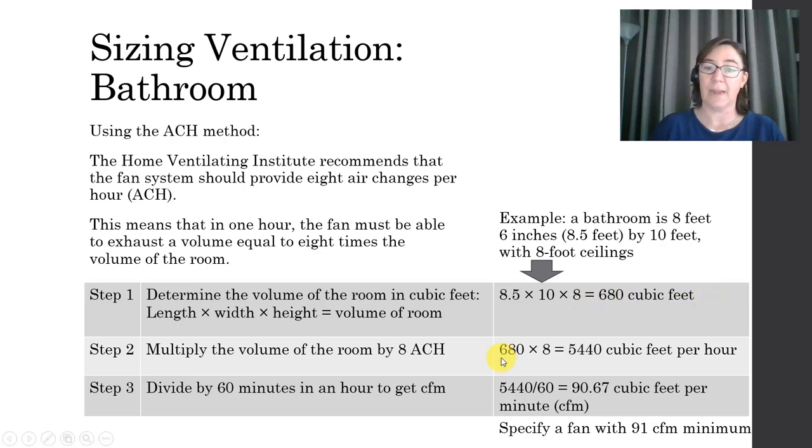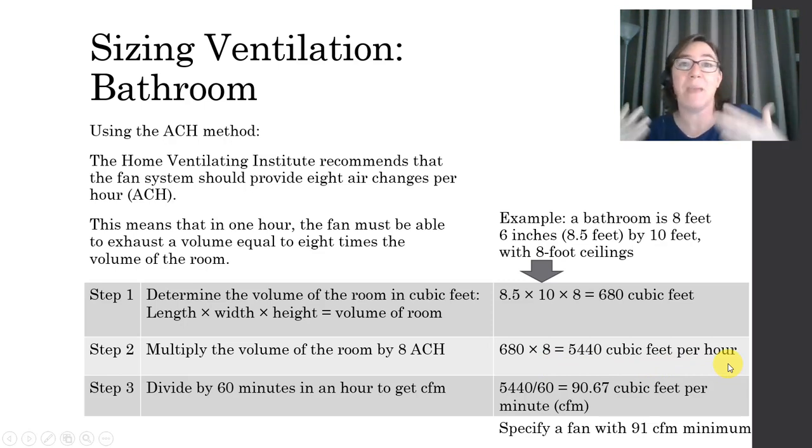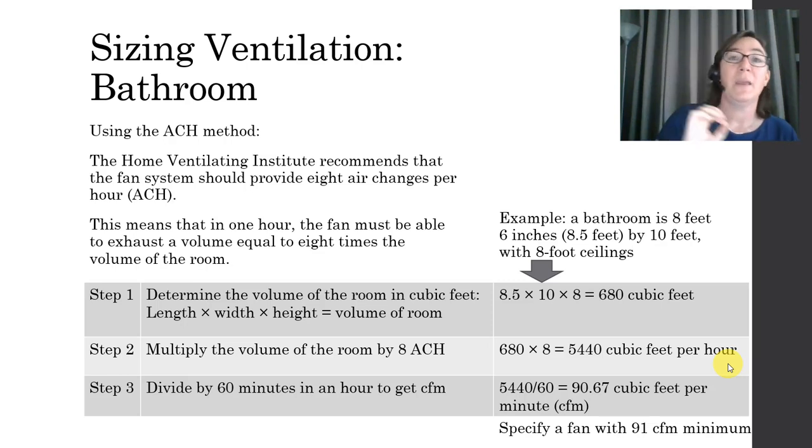All right, so 680 times 8, we get 5440 cubic feet per hour. All right, but fans are not rated in cubic feet. They're rated in cubic feet per minute. Bathroom fans are not rated in cubic feet per hour. They're rated in cubic feet per minute.